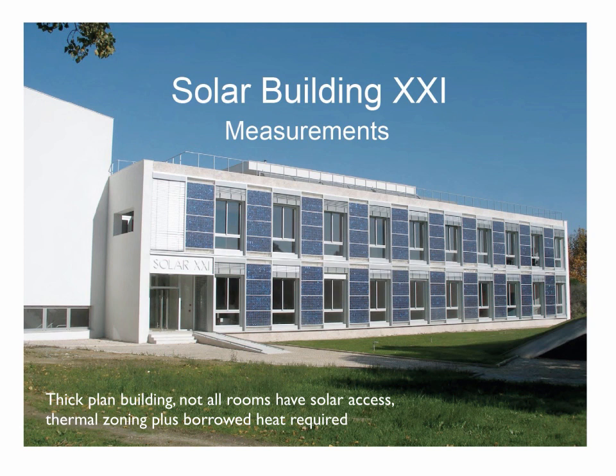Here's a building that's a bit thicker: Solar Building 21, a research building in Portugal. Not all rooms have solar access, so we use thermal zoning and need to borrow and move heat. On the south-facing facade, you've got direct gain windows alternating with photovoltaics in the vertical plane. The PV panels are only about 15–18% efficient — what's left is ordinarily waste heat going to atmosphere. In this case there's an airspace behind, making it a combination PV system and air collector that recovers the waste heat from behind the panels.